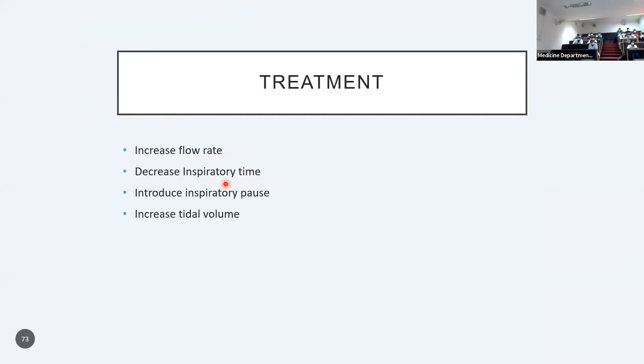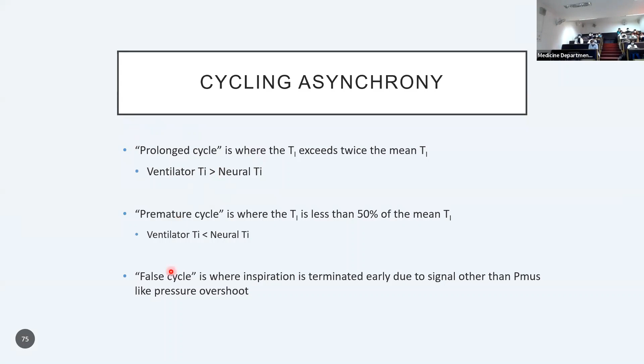Prolonged cycle is when the ventilator TI is more than the neural TI. That is, the patient wants to stop the breath and start expiration, but the ventilator is not allowing him. The ventilator is prolonging the cycle. Premature cycle is when the ventilator prematurely cycles into expiration, but the patient still wants to continue inspiration. And then we have false cycling, we'll see later.